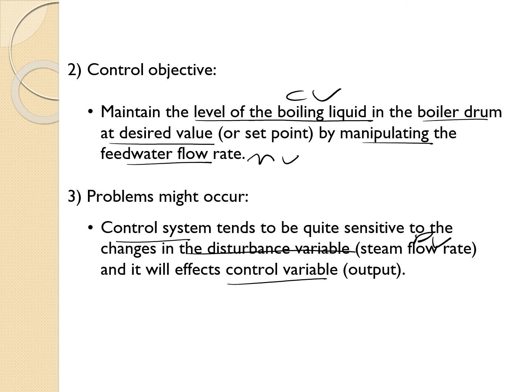So for the feed-forward control loop scheme, like what I said before, we need to measure the disturbance variable and make the correction on the manipulated variable, right? So this FT will measure the steam flow rate in. This is the flow rate transmitter, and we send the signal. Actually, this dash line is an electrical line. Why do we use an electrical line? Because basically the controller itself is a digital controller, so it only receives electrical signals. So we have to convert here. This transmitter converts the pneumatic signal to an electrical signal.